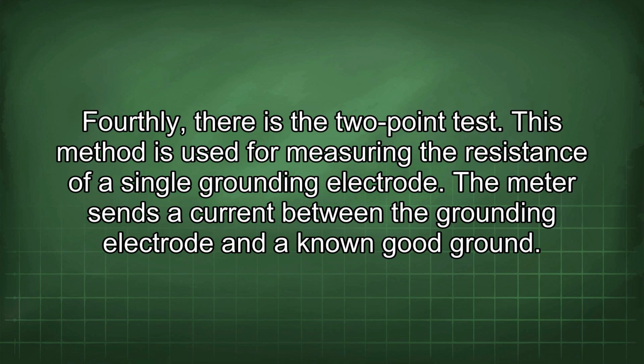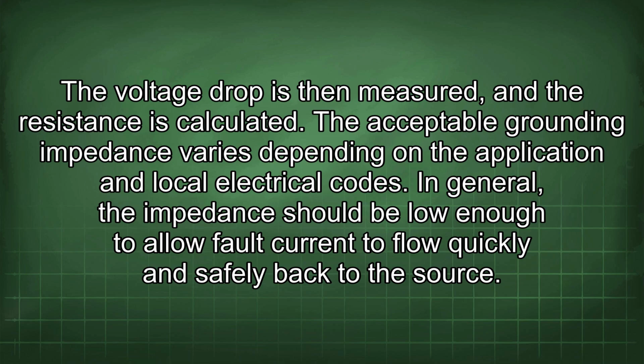Fourthly, there is the two-point test. This method is used for measuring the resistance of a single grounding electrode. The meter sends a current between the grounding electrode and a known good ground. The voltage drop is then measured, and the resistance is calculated.